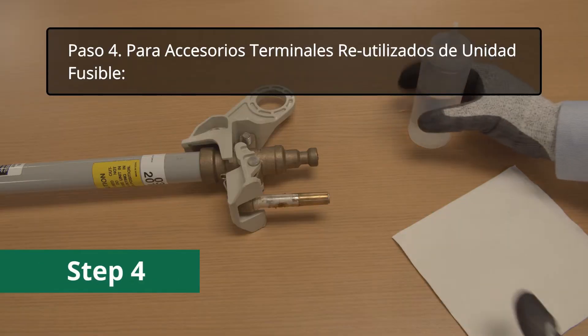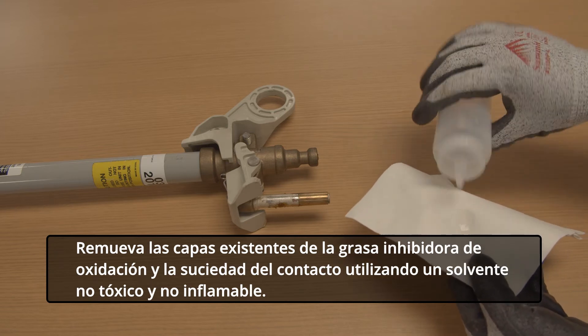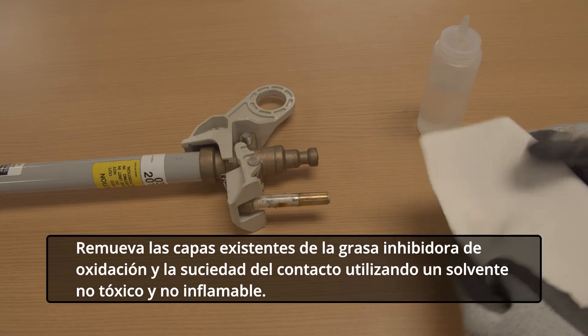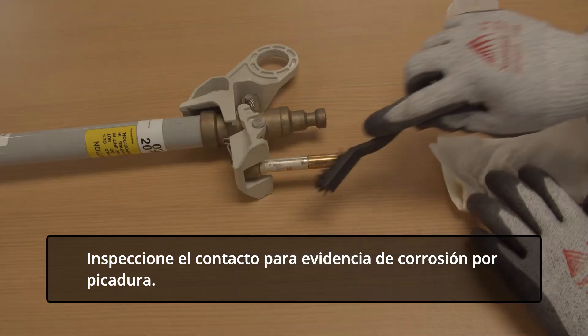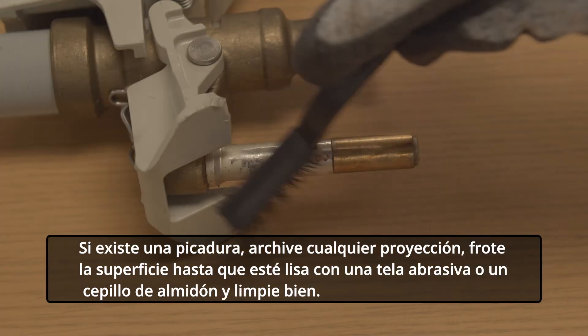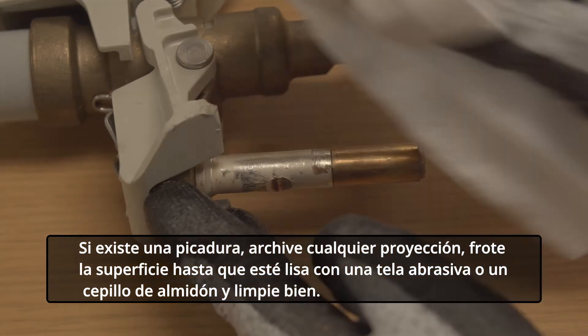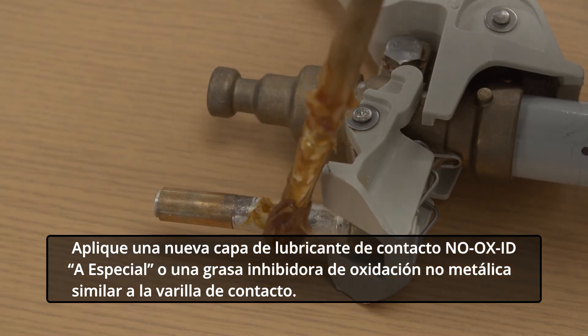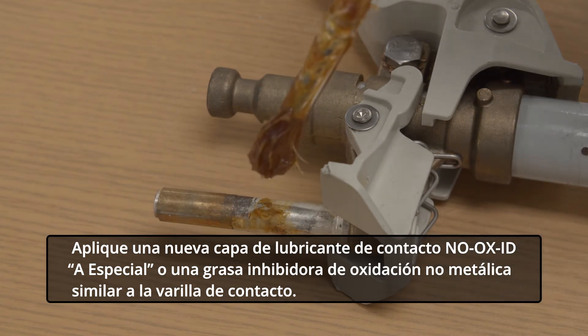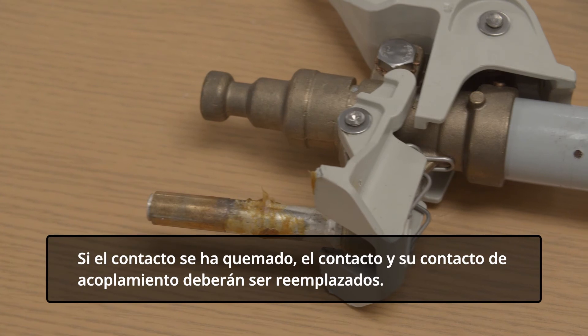Step 4. For reused fuse unit end fittings, remove the existing coating of oxidation inhibiting grease and dirt from the contact using a non-toxic, non-flammable solvent. Inspect the contact for evidence of pitting. If pitting has occurred, file down any projections, abrade the surface until smooth with an abrasive cloth or scratch brush and wipe clean. Apply a new coating of NO-OX-ID A-Special contact lubricant or similar non-metallic filler oxidation inhibiting grease to the contact rod. If the contact has been burned, the contact and its mating contact should be replaced.